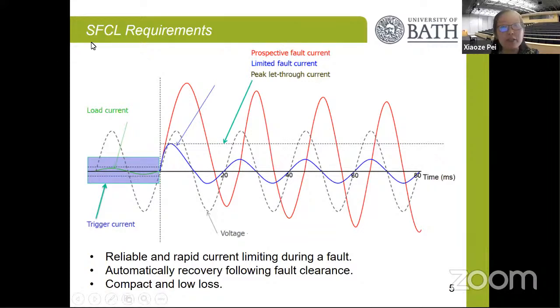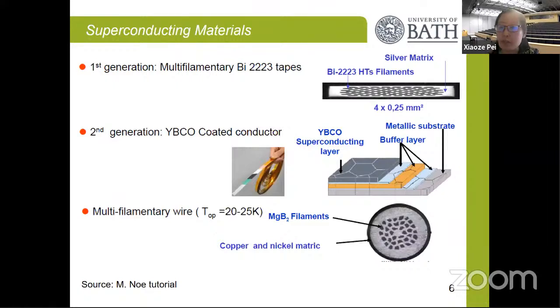So why are we talking about the superconducting fault current limiter? Because superconducting material has very high current density, and also it doesn't have losses under DC operating conditions. So what is the commonly used superconducting material for the fault current limiter application? It is mainly what we call high temperature superconductors. These can operate in liquid nitrogen, because nitrogen makes up 78% of the air, so it is very easy and cheap to get liquid nitrogen. And the first generation high temperature superconducting material is the multi-filament BSCCO 2223 tape. And Sumitomo in Japan is one of the leading suppliers of this tape.